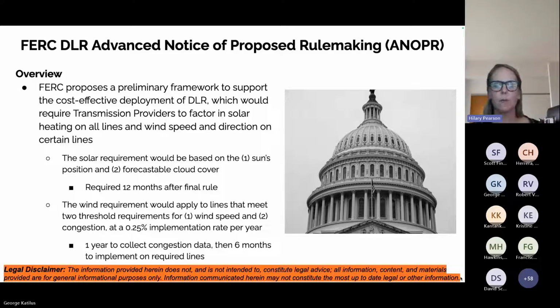So as demand rises in the late afternoon timeframe and the sun is setting, it's also when we generally see wind speeds rising, which can provide thermal cooling to transmission lines. I think it's exciting to potentially see the use of DLR help address some of these periods of peak demand on our system.